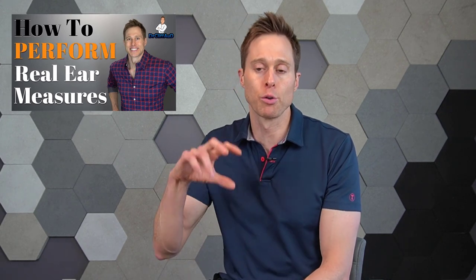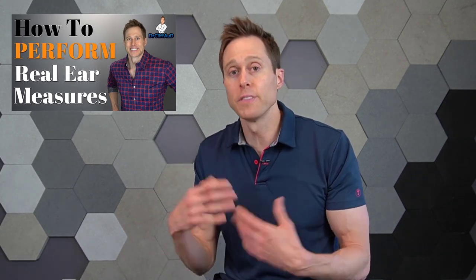Still at this point, I don't know for certain, so what we have to do is hook them up to real ear measurement. A lot of you have heard me talking about real ear measurement before, and I have videos on it. If you do not know what real ear measurement is, go watch those videos, because it is one of the most critical pieces of verification to make sure your hearing aid is programmed correctly for your hearing loss prescription. I hook the patient up with their hearing aids in their ears, with the verification equipment set up properly, and do a measurement of the amplification inside their ear canals, matching it up on screen to see how close or how far off of their prescription they are.